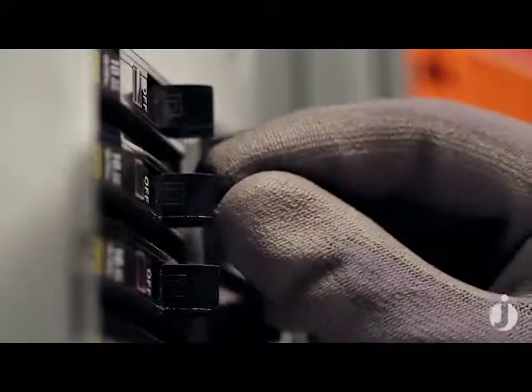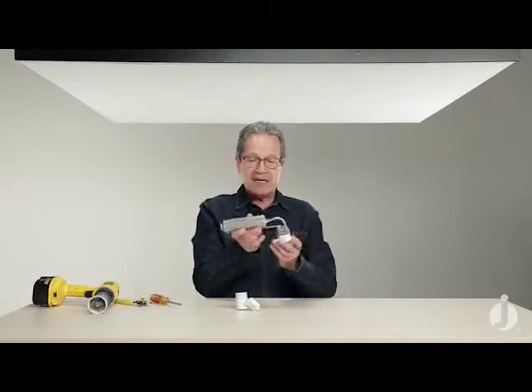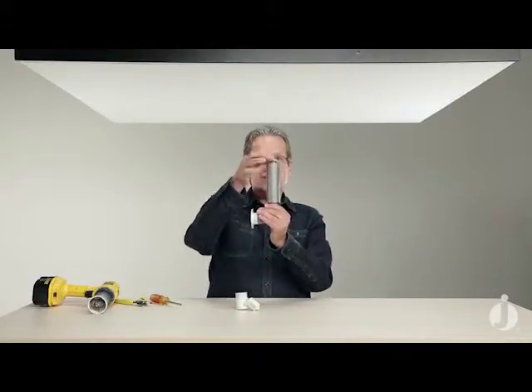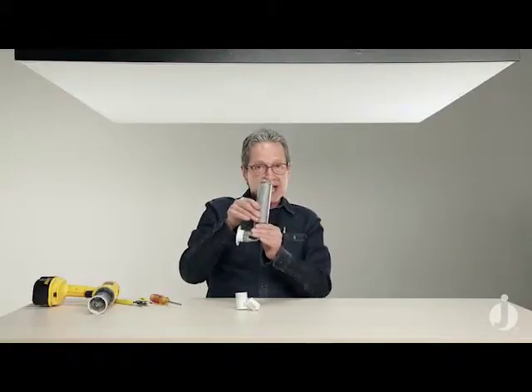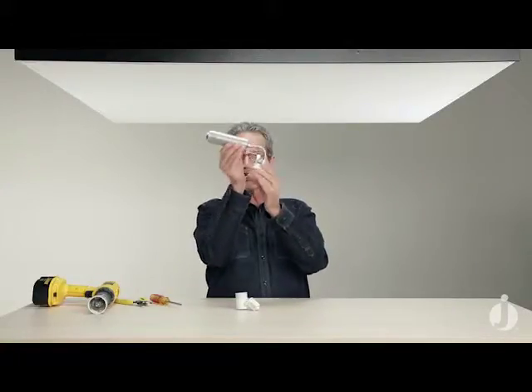So let's begin our installation. I've already had our house electrician bring power to the installation. Naturally, the power has been turned off at our circuit breaker panel. Next, we need to drill a 2-inch diameter hole. But before we begin that, we need to make sure that there's no insulation present in the ceiling. We need a minimum of 6-inch depth, and that is to accommodate the distance that our wiring chamber takes as we push it up through that 2-inch hole.